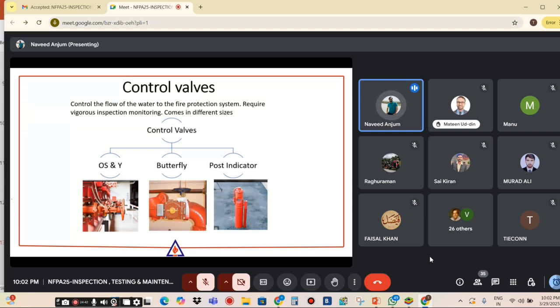This is also important because we forget to test the control valves. Why is it important? When we need maintenance of the system, during corrective maintenance, preventive maintenance, any type of maintenance, we are required to close these valves. But mostly when we try to close these valves, they are passing because we are not testing them every year or at a proper interval. So these are different types of control valves, and why. Hopefully you know very well about it.